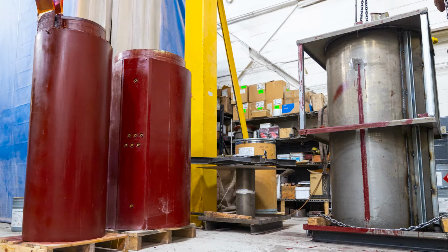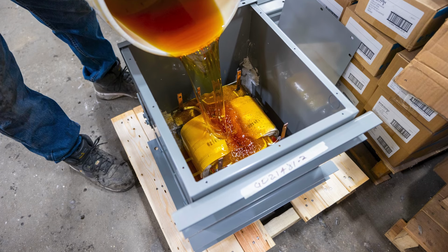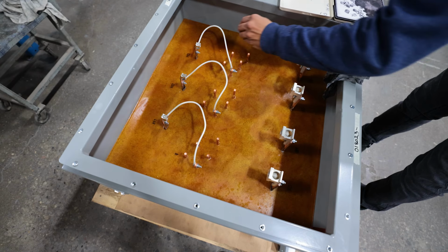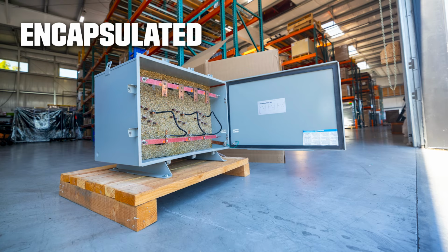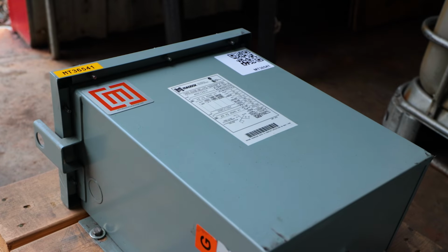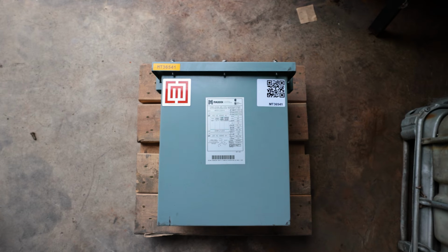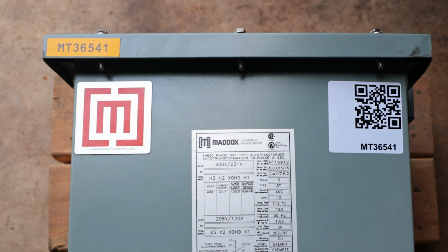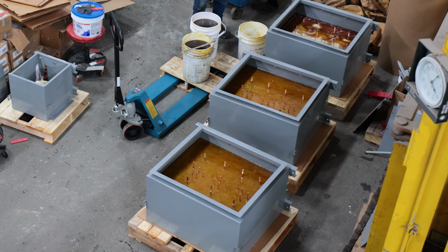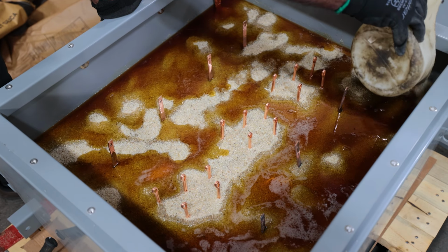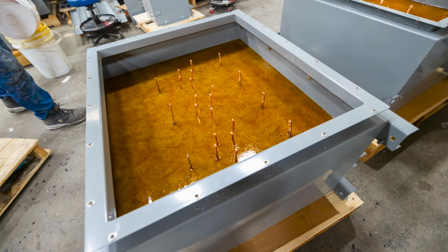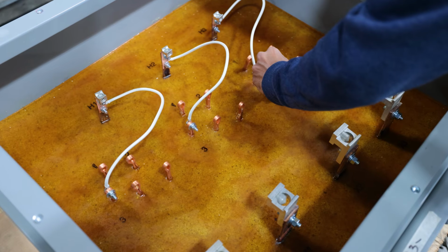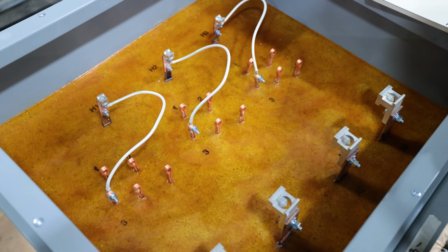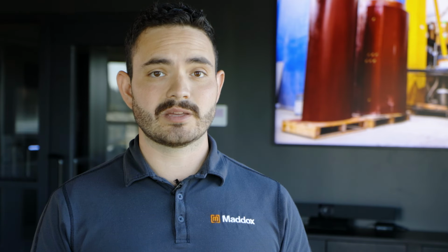Their windings are sealed in epoxy resin, giving them extra mechanical strength and environmental protection. The two main types are encapsulated and cast coil units. Encapsulated transformers are small, resin-filled units used for voltages under 1,000 volts. Their smaller size means the entire enclosure is filled with epoxy. Once cured, the windings are locked into a solid block, leaving only the tap leads and terminals exposed. These units are small enough that some can be wall-mounted.